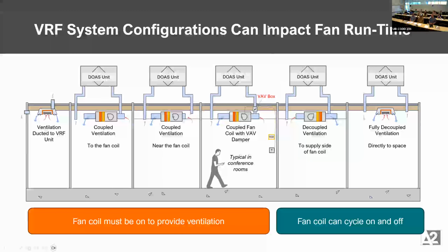Neil, I think you mentioned that on the fan coil side, you just have it auto-sized. Do the same thing on the outdoor unit, on the compressor? We will early on. I would say if you actually know the size of your outdoor unit, it's probably best to size the outdoor compressors and put in the exact number of compressors, because you can do capacity, number of compressors, and then overall turn down. And those are pretty important and specific. The indoor fan coil is probably best to auto size.